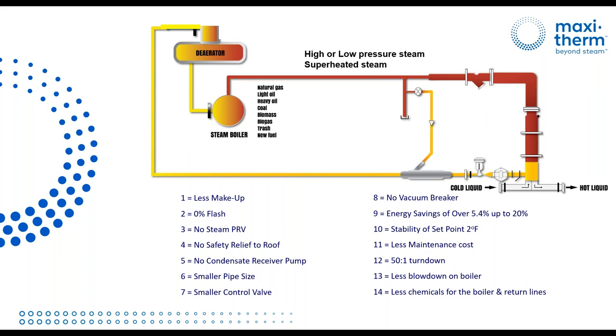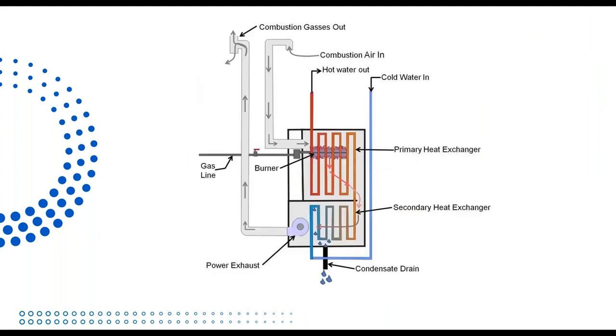Energy saving up to 20%. This I will show you very soon. Stability of set point within 2 Fahrenheit, less maintenance costs, 50 to 1 turn down ratio with one little control valve. Less blowdown on the boiler, less chemical also at the boiler for the return lines. We're not going to cover this in detail today, but these are the highlights of going 100% closed loop.